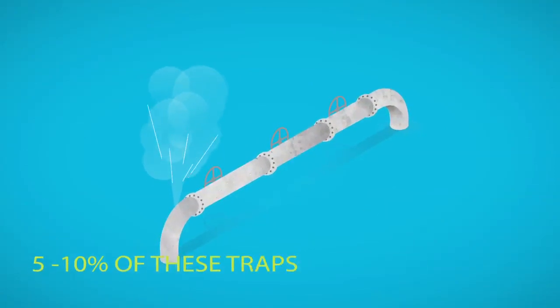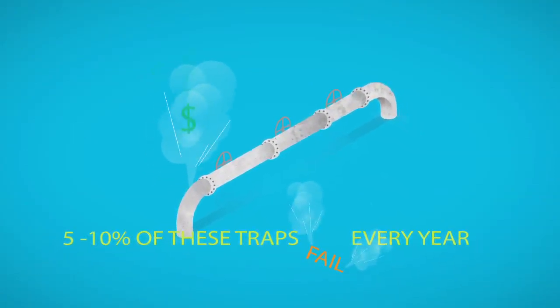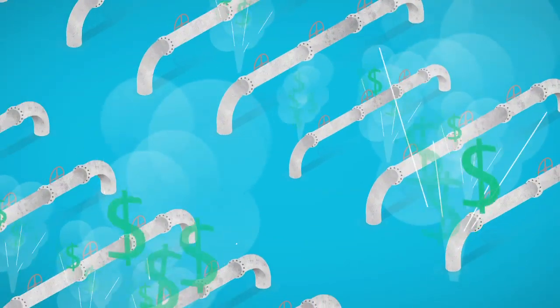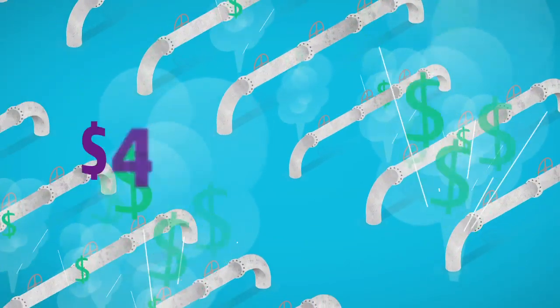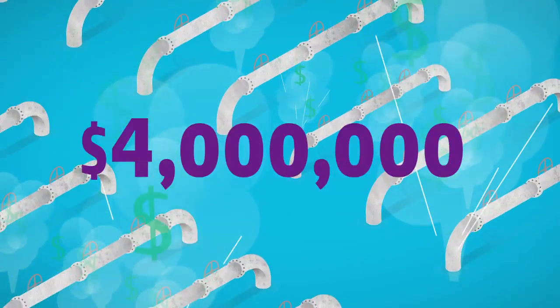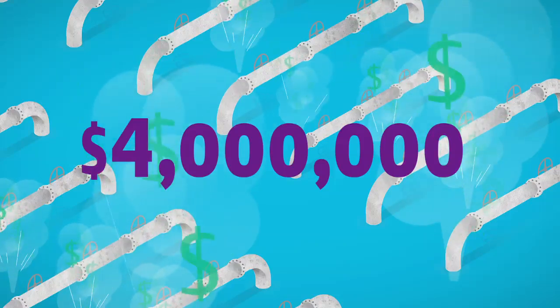5 to 10 percent of these traps fail every year, and when they do, money literally disappears. Lots of money. A typical refinery loses nearly 4 million dollars in energy costs every year because of malfunctioning steam traps.